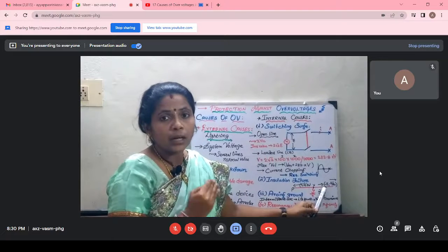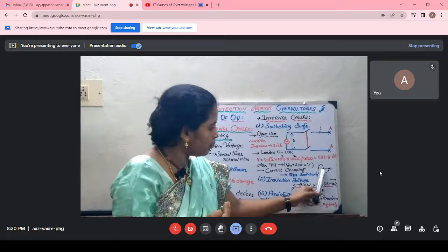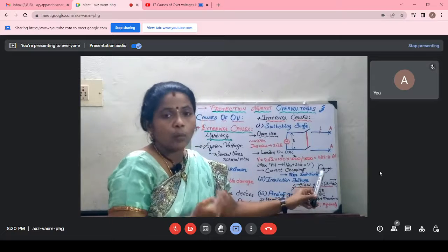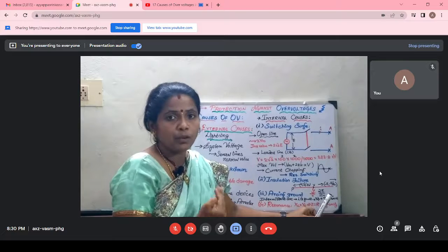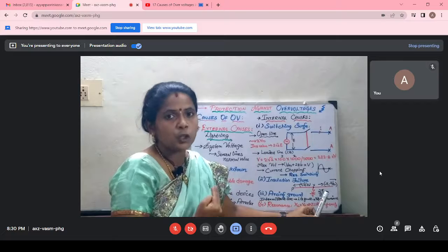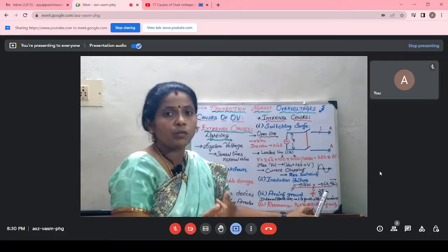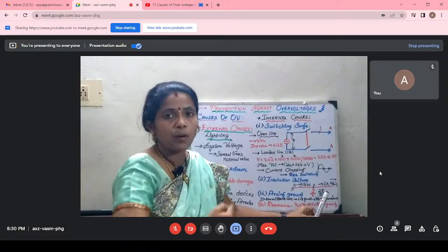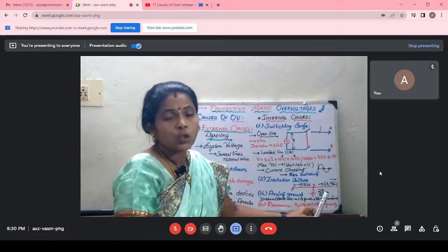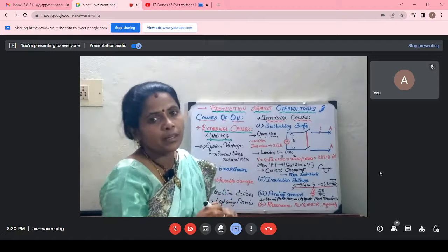But if you quench the arc before the natural zero, this process is called current chopping. What will happen? If I quench before the natural zero, there is a problem of restriking again. So you will again have a high steep of voltages which is penetrating.